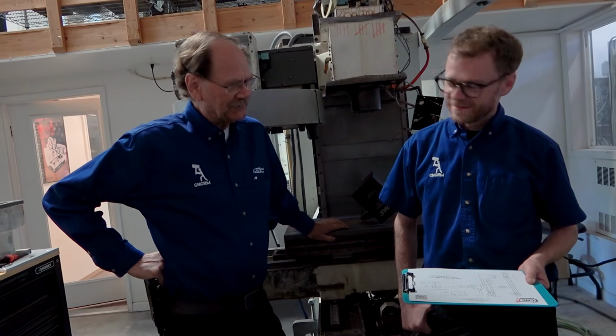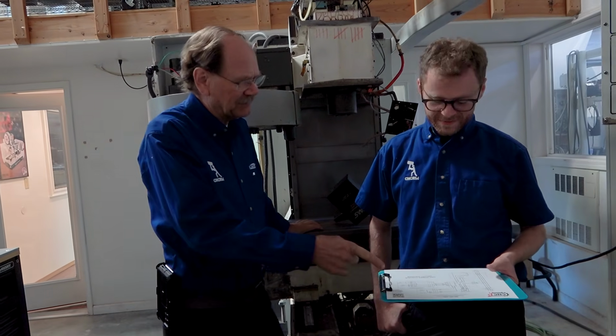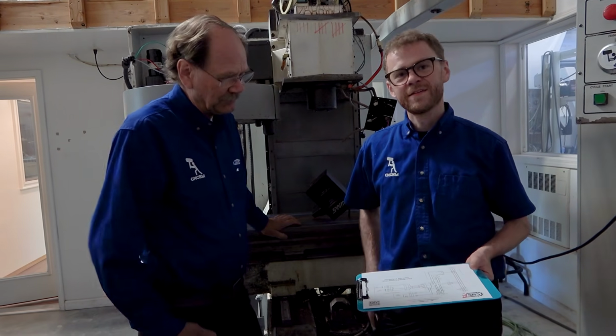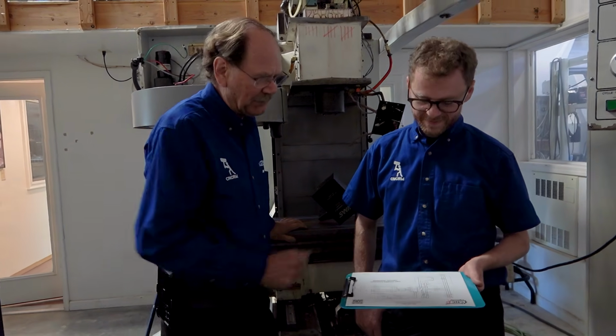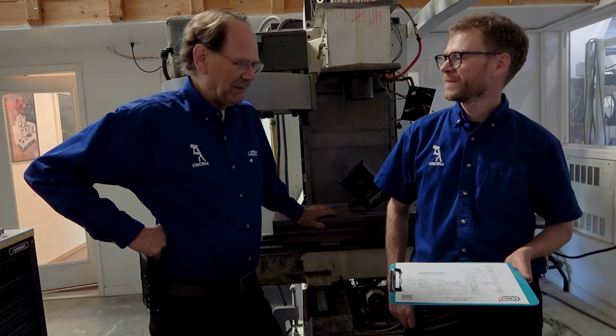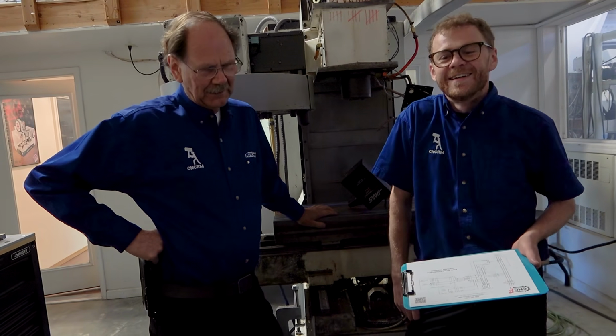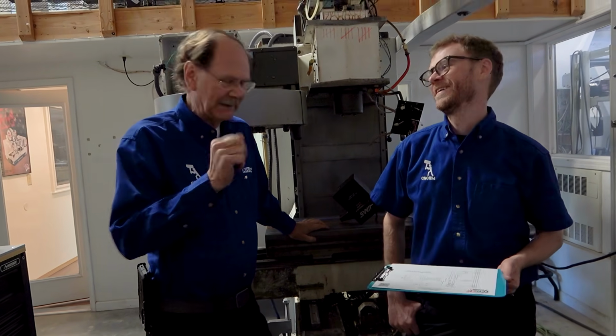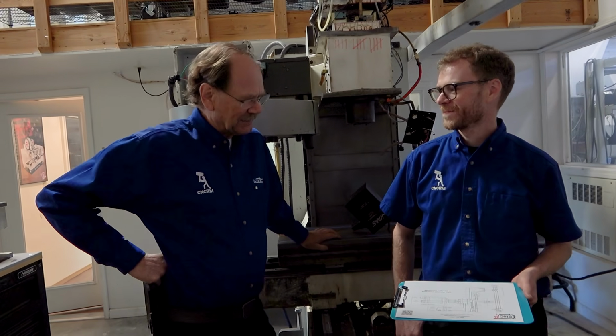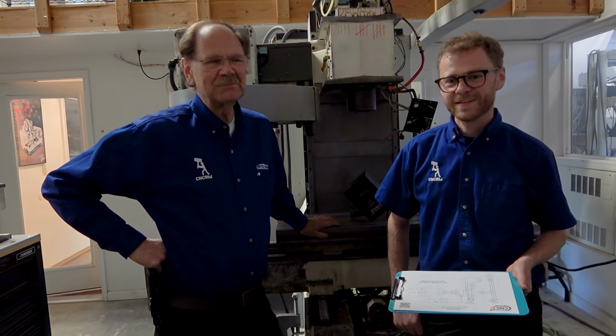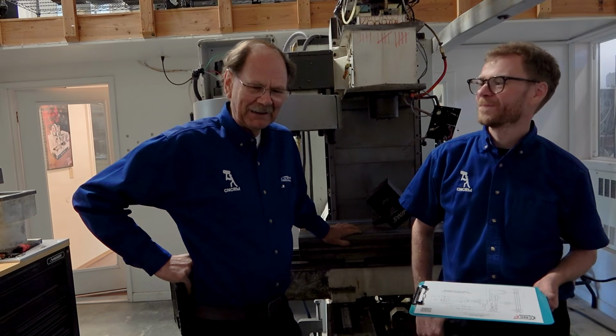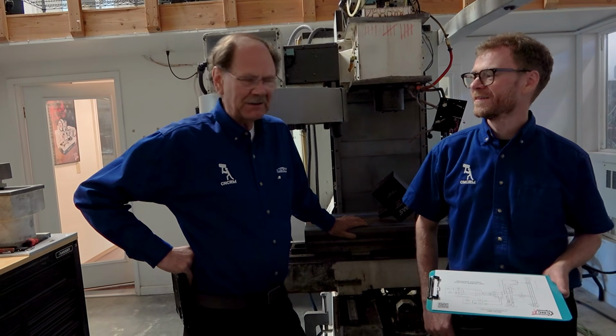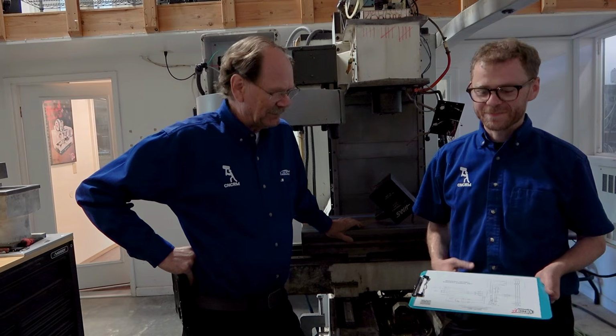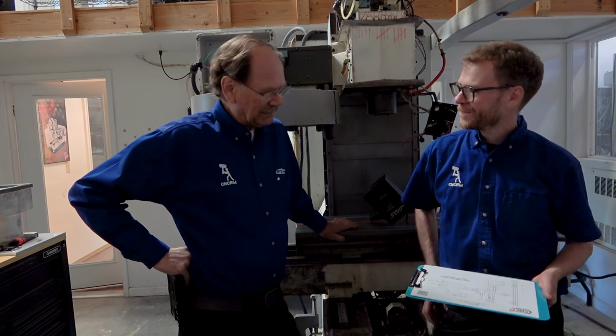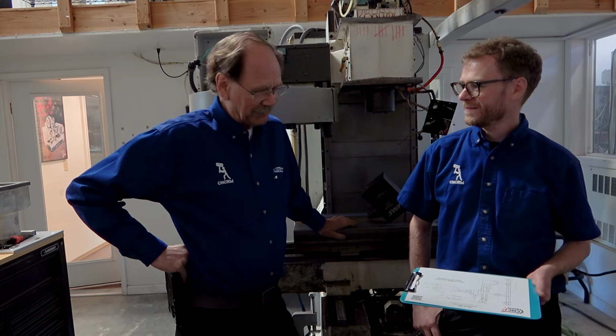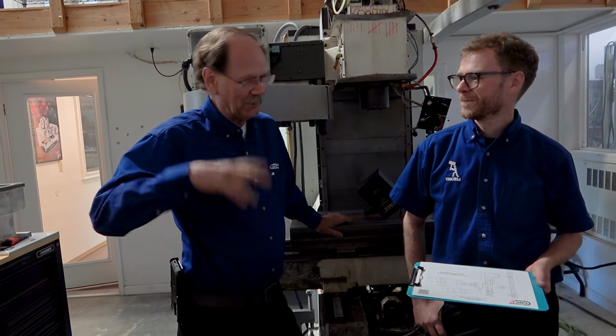So we had to start troubleshooting the machine. The first thing - if you're troubleshooting or teaching, don't go in the back of the machine, take everything out, inspect it all, and put it back in, because that's what they did. They took out every single circuit board in the machine, put it all back in, and failed to check if any of the cables were marked or labeled, which they weren't. They couldn't get the machine to run and were in a big sweat because they were writing this manual with all these people there.